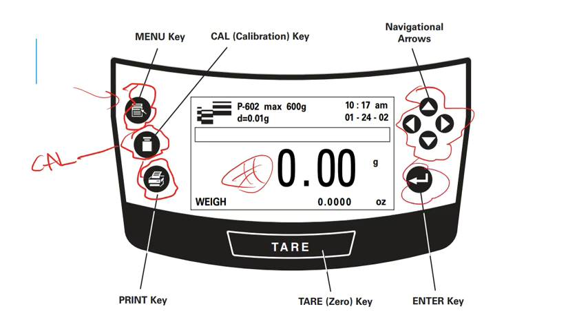And then finally, an enter key. That's very often used in the menu option to accept a certain answer that the balance is asking you. That is an enter key, just like it's an enter key on your keyboard at home on your computer. Finally, the biggest, most important button is down here at the very bottom, and that is the tare button. So the tare button is the 0 button. Whenever I go to the balance, I always make sure that it is tared, that it is reading 0.0000. I press that button and I wait. And what I should see on the screen is, sure enough, 0.0000, or however many decimal places that balance goes to.